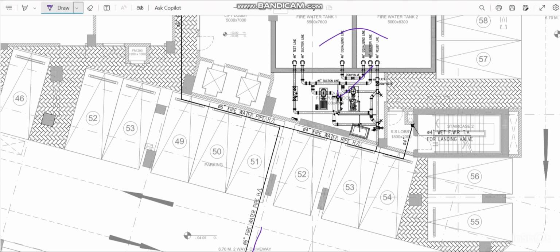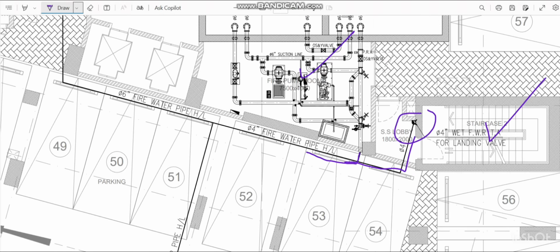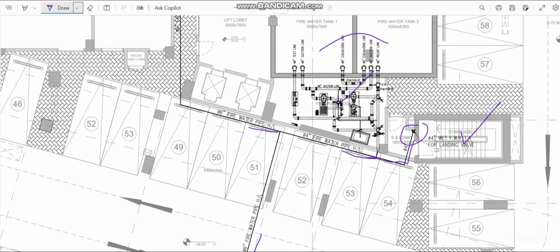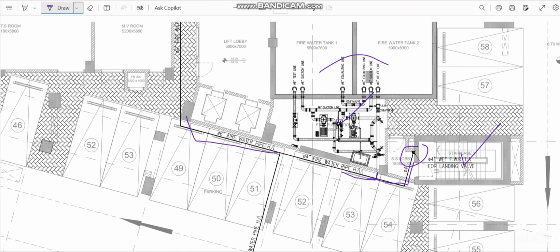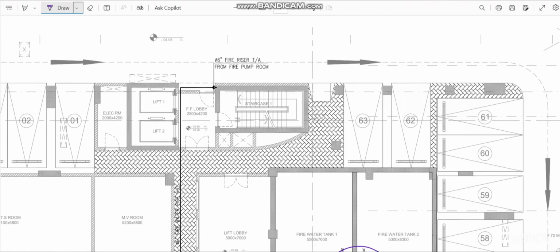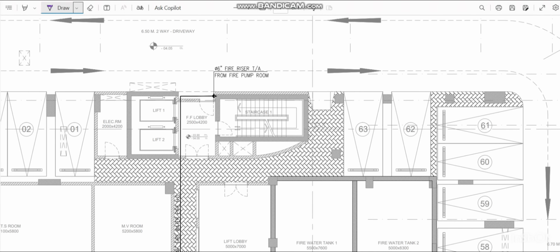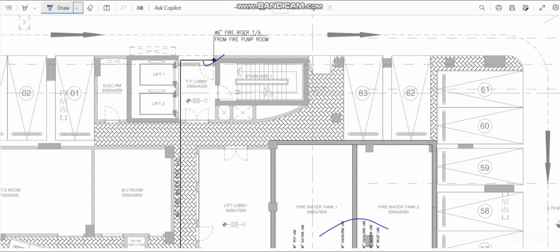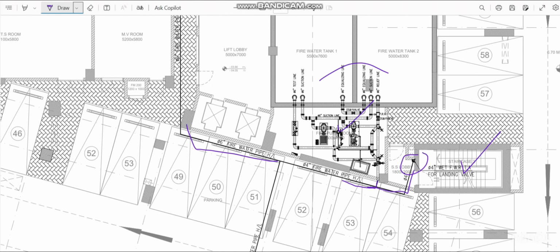So from the fire pump room, you can see two distribution lines going. One line is for the separate riser. I told you the riser diagram. One riser is only for the landing valve. So if we have one stair here, from top to bottom we have the landing valve at this point, and we have another line which is going here. So this riser is called a combined riser. Combined riser means we have the landing valve, the fire hose cabinet, and the sprinkler system. All of this is served by this riser, and this riser is only for the landing valve.